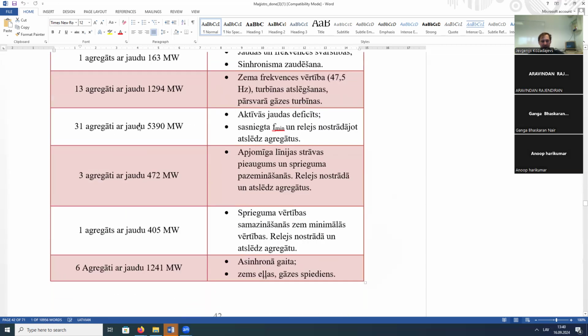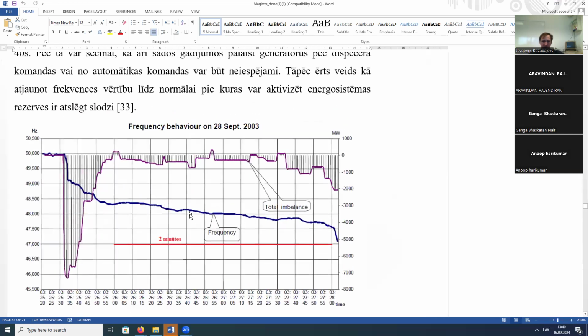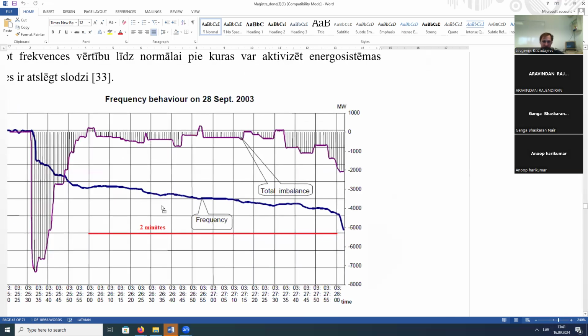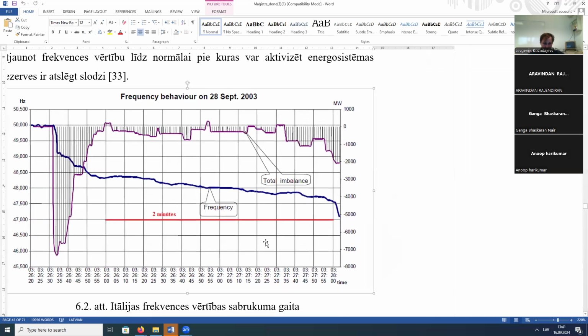And let's come here to look at this diagram, because this diagram shows in more detail what is going on. Here we see the frequency. This purple is imbalance, this blue is frequency. Here we could see the imbalance, the values of power. You see Italy is disconnected and the total imbalance is these 7 gigawatts. Here we see the time for under-frequency automation operation. To this time we see how the frequency dropped. The under-frequency automation activated and started to disconnect the load. If we disconnect the load, it means that the imbalance is decreasing.